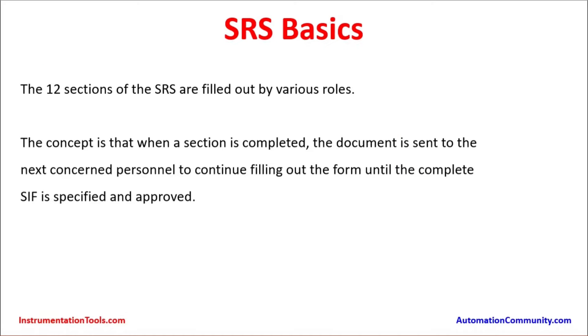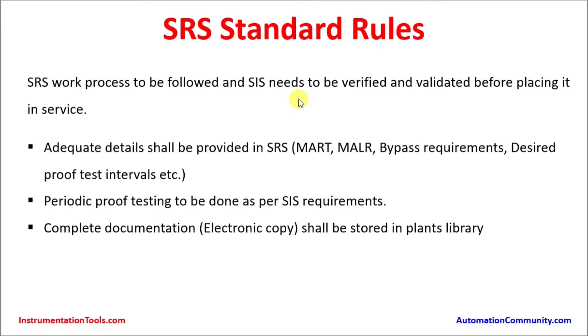The SRS has 12 sections. The concept is that when a section is completed, the document is sent to the next concerned personnel to continue filling out the form until the complete SIF is specified and approved. The SRS is for each SIF, so the 12 steps must be completed in sequence — whenever one step is completed by a particular department, it goes to the respective department or personnel to address the next step. The SRS work process must be followed, and SIS loops need to be verified and validated before placing them in service.